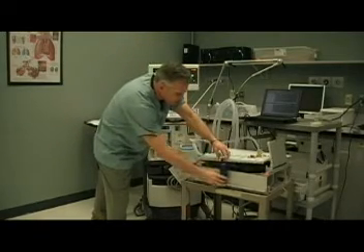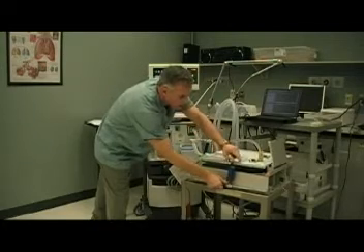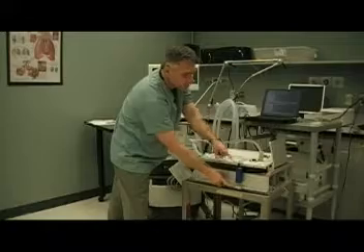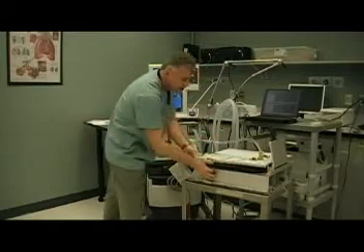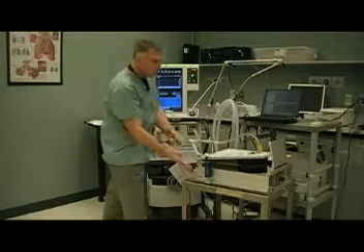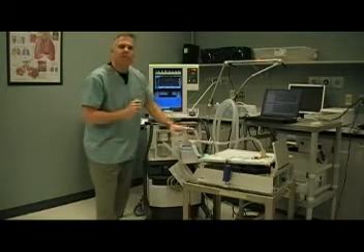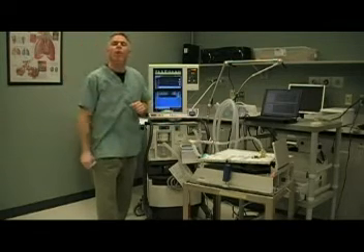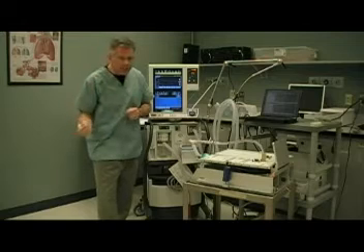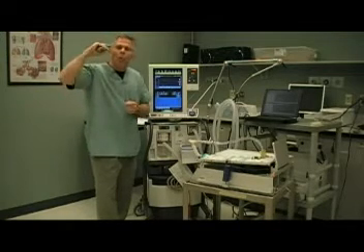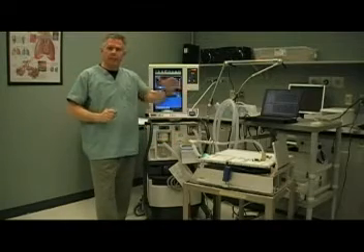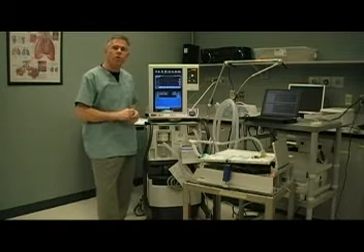This mode is different in that as patient lung characteristics change — whether compliance decreases or increases — the pressure being delivered to the lungs will remain the same. Unlike volume ventilation, we are specifically controlling the pressure, and volumes and flow rates are allowed to vary. In volume ventilation, volume and flow were held constant and pressure could vary; in pressure control, pressure is held constant and volume and flow vary.